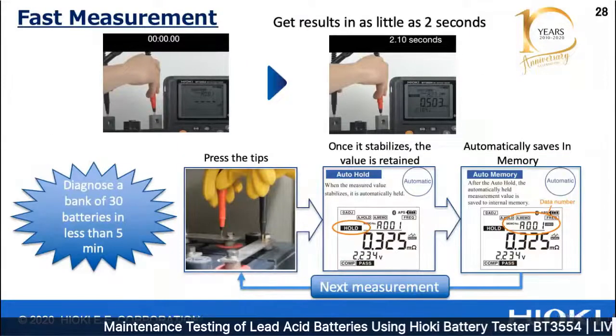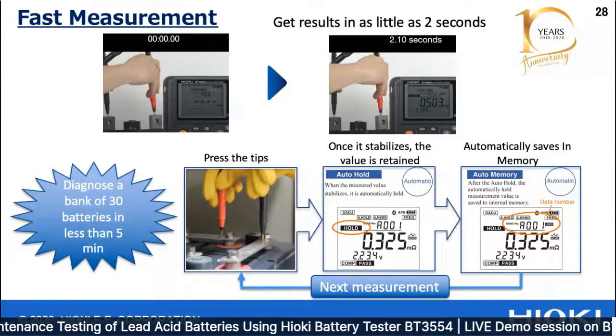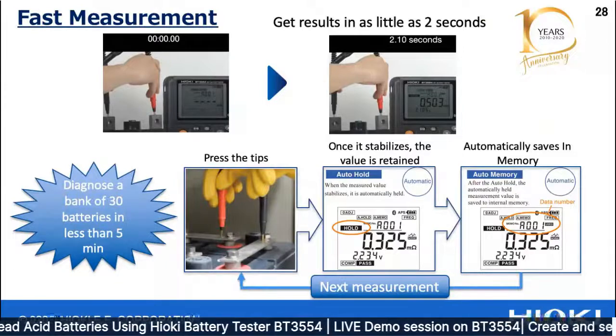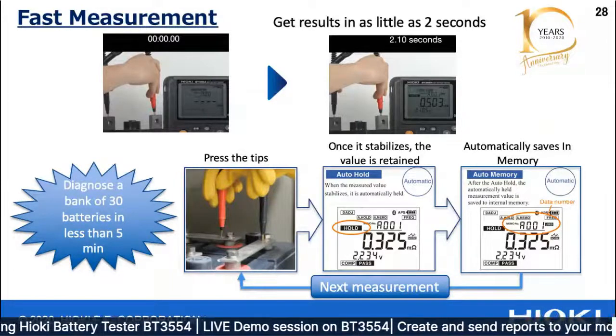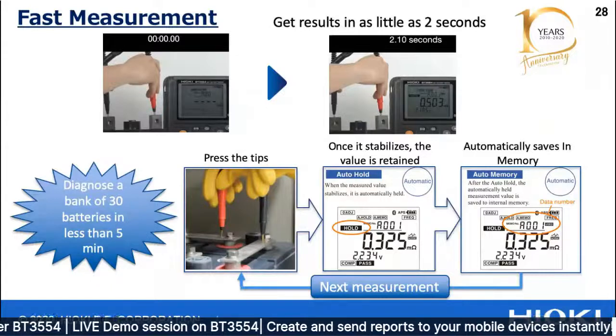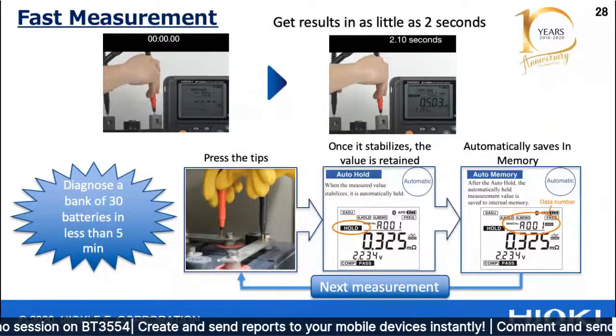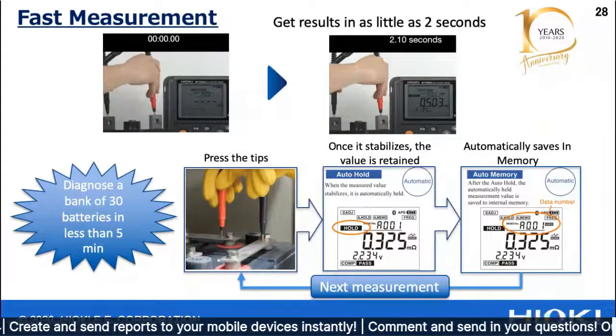Another important feature is the fast measurement time of our battery tester, the BT3554. It's able to measure resistance and voltage and store the value in memory within 2 seconds. That's very, very fast.